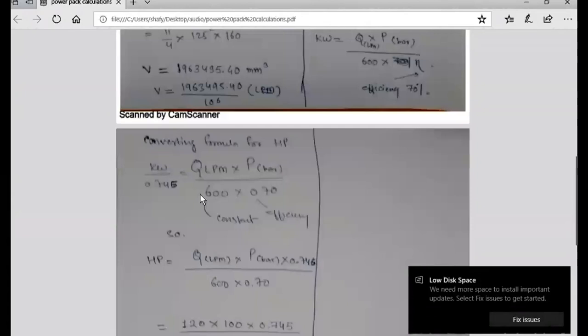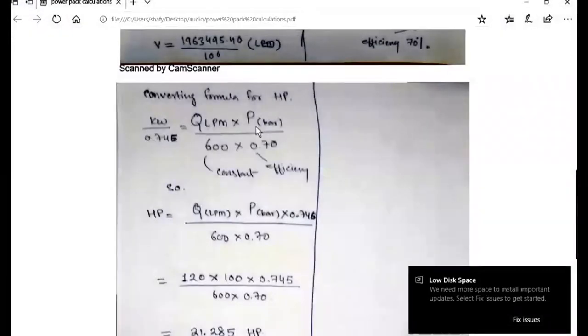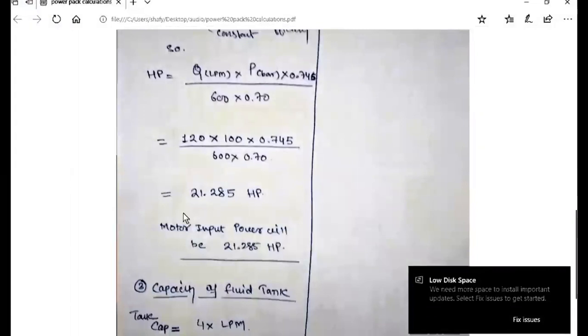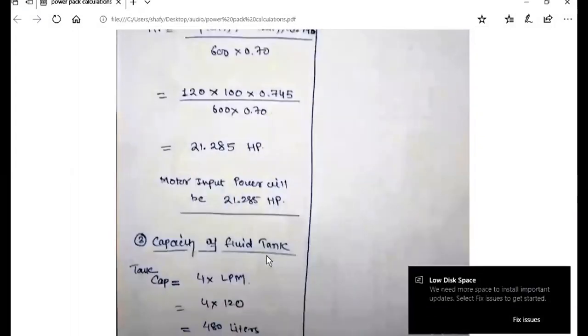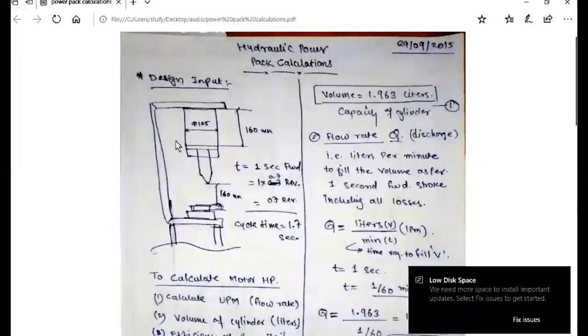After calculating and putting all this in, kilowatt, if we convert into horsepower, we'll divide by 0.745 and you get the answer as 21.285 horsepower. That is our horsepower. And to calculate the capacity of the tank, it should be four times LPM, so four into 120, that is 480 liters should be the tank capacity.